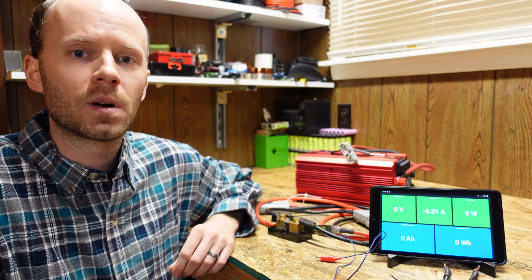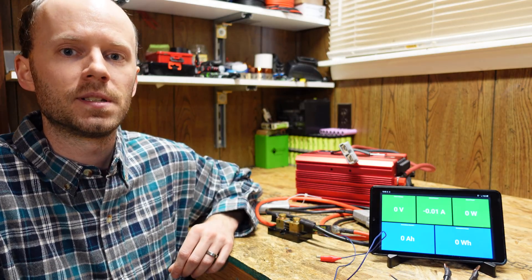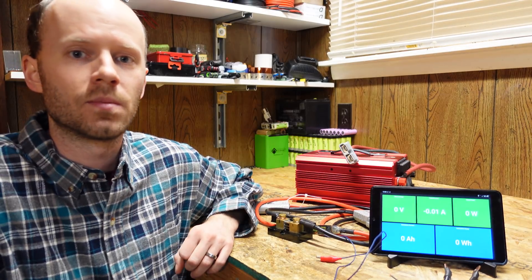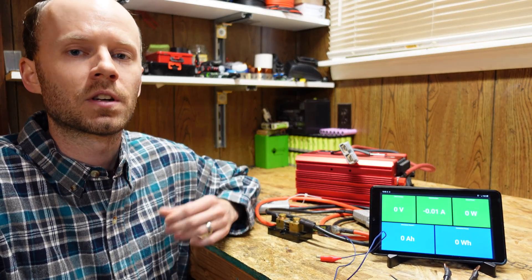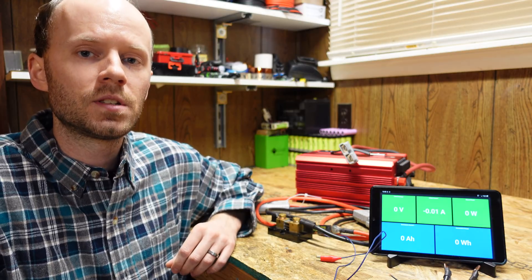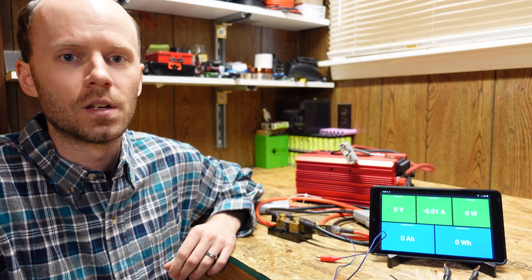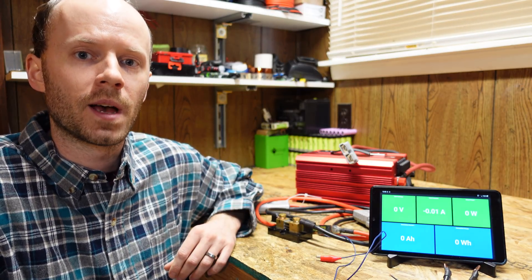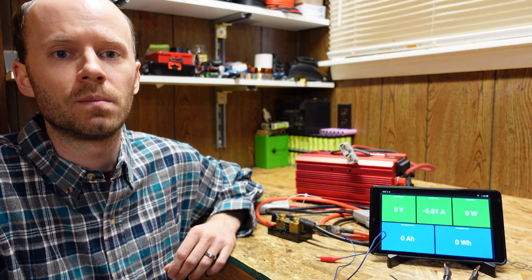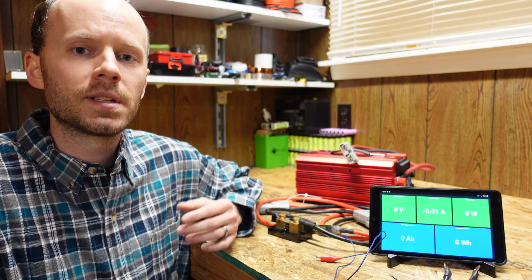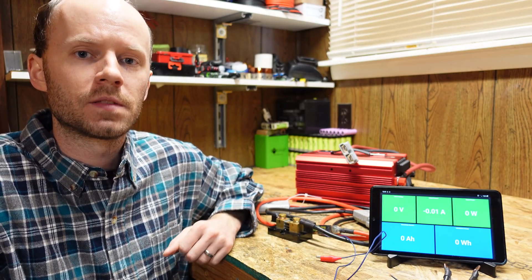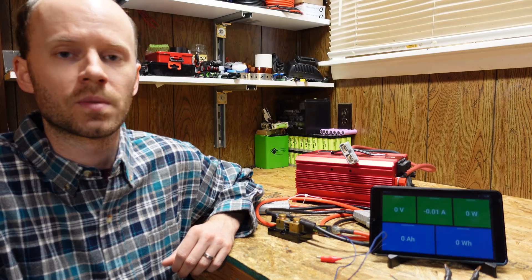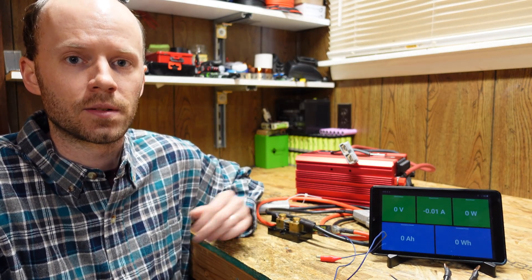Those tests are typically done with what's called a certain C rate. In the battery market, the fairly standard accepted test is a 0.2 C rate. So to calculate that out, you would take the 0.2 C rate and multiply that by the amp hour capacity of the battery. So if we have a 100 amp hour battery, a 0.2 C rate would be 20 amps. Every battery cell will have a technical data specification sheet that tells you what the standard charge and discharge rates are that they used when they tested these batteries in the factory.